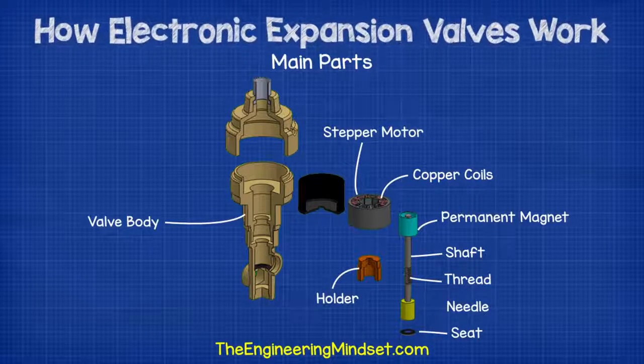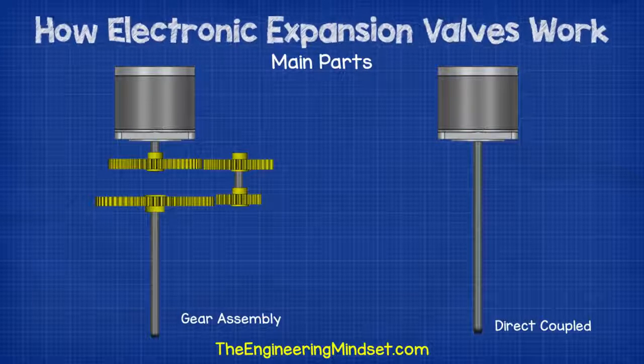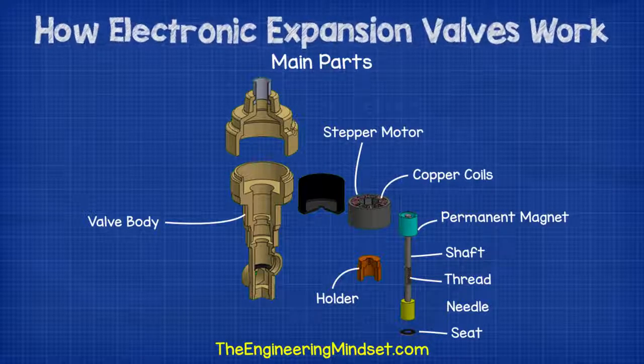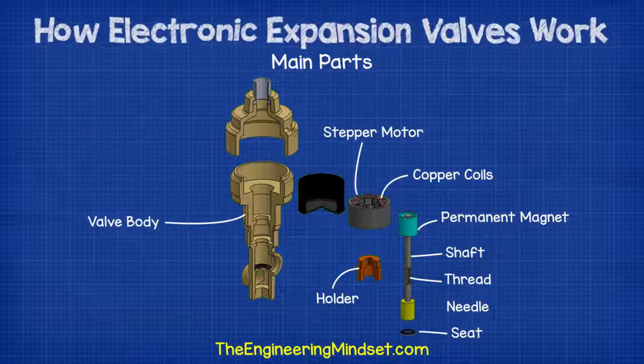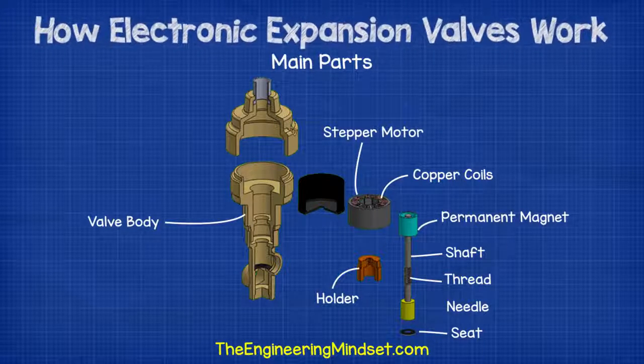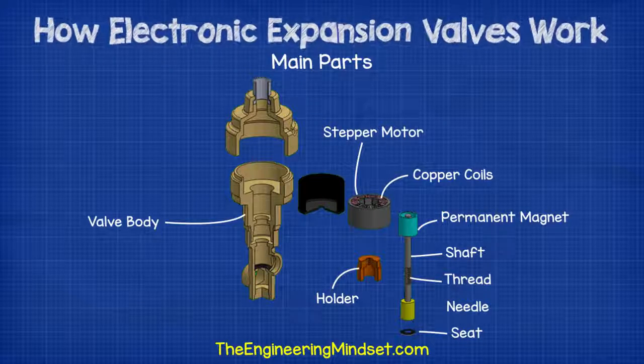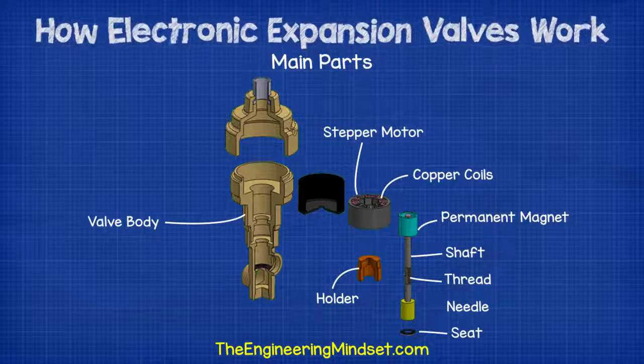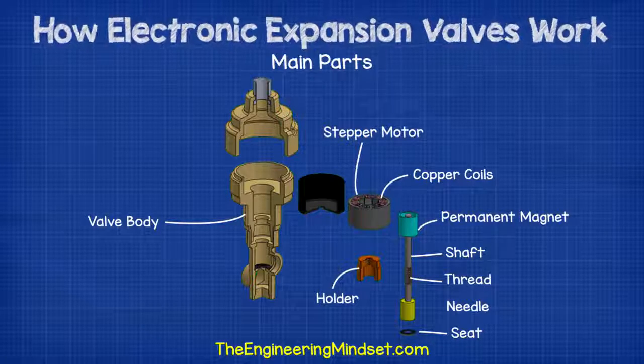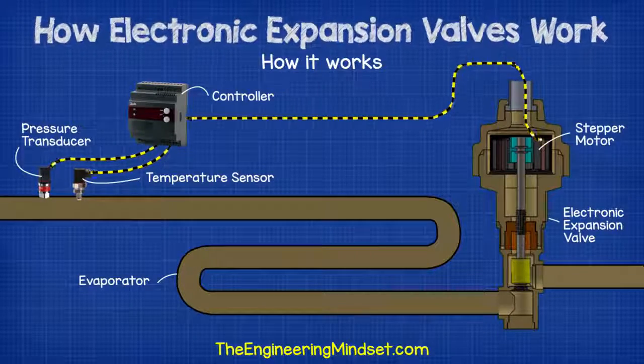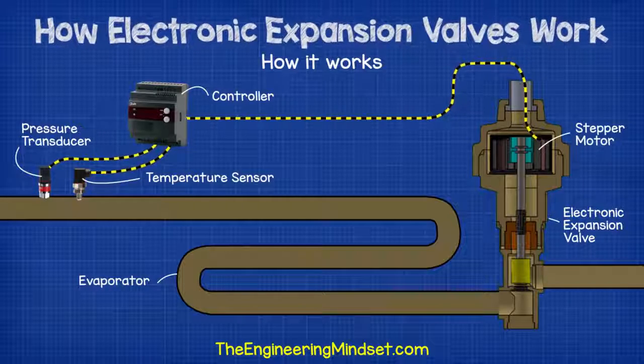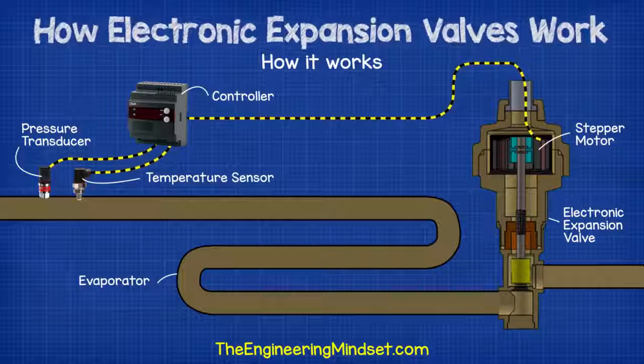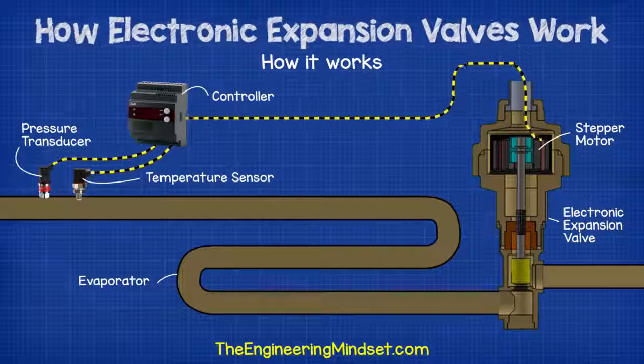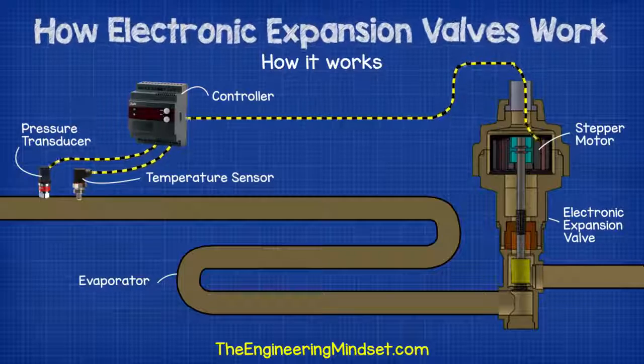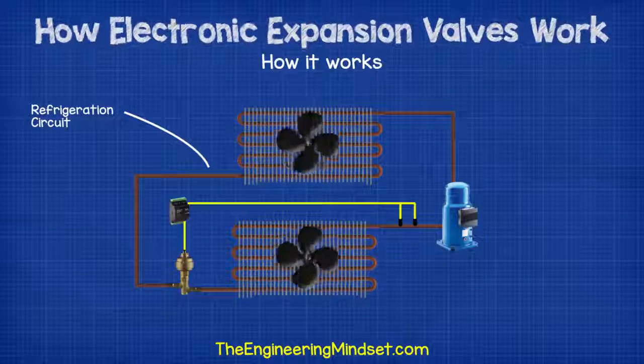Attached to the permanent magnet there's a shaft. Now, some designs will use a gear assembly between the motor and the shaft, but as we're only looking at a simplified example, we're going to stick to a directly coupled shaft. On the shaft is a thread. This thread sits within a holder which is attached to the valve body. At the end of the shaft is a valve needle. Then we have the valve seat, which the needle moves into and out of to close and open the valve and control the flow of refrigerant. We'll also have some temperature and pressure sensors to take measurements of the refrigerant in order to calculate the superheat. These will be connected to the controller. The controller is then connected to the stepper motor and will tell it how much to open or close to maintain the correct superheat.